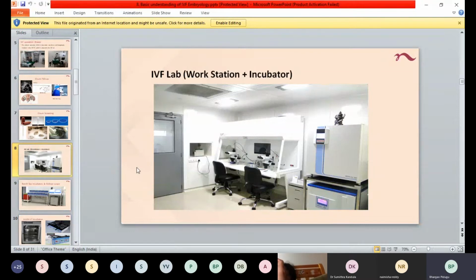IVF lab workstation and incubator. Here you can see the hatch which connects the IVF lab and the OT, where the ovum pickup is done in the IVF OT, and it is put in the dry test tube warmer here. And then we have a workstation. Here the person who scans first sits, and here the second person takes charge. It is always advisable to have the incubator closer to your workstation, be it laminar airflow or a micromanipulator. The distance is very essential, because if you are holding a dish and walking for a long time, a temperature drop can take place. So it is always advisable to have the incubator right beside your workstation or your manipulator.